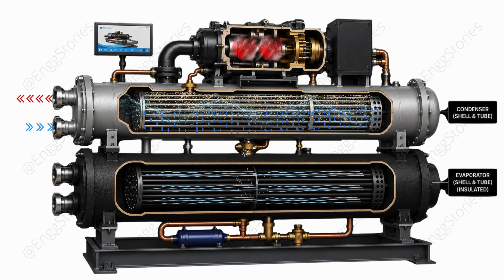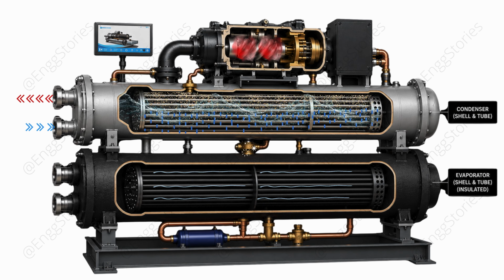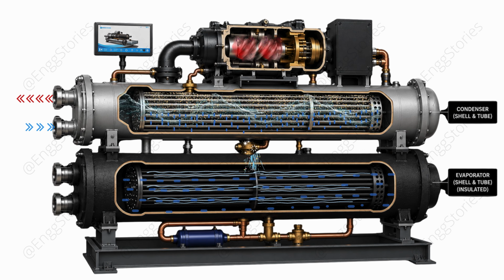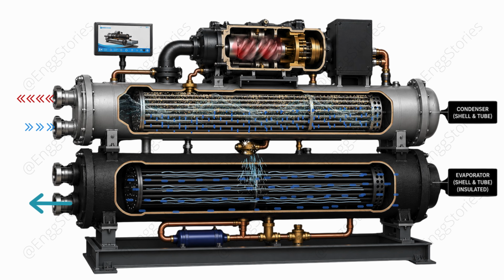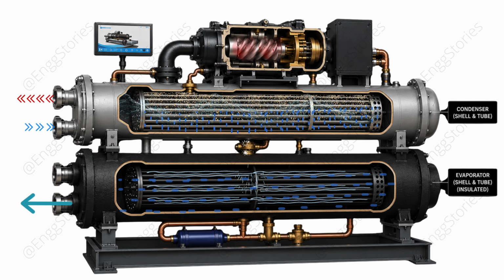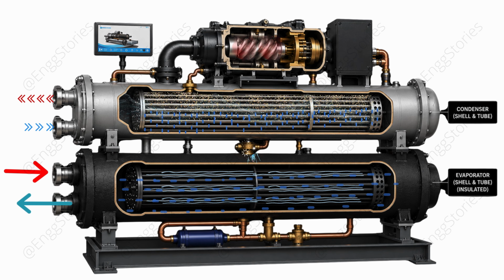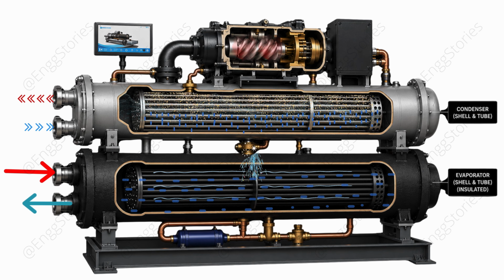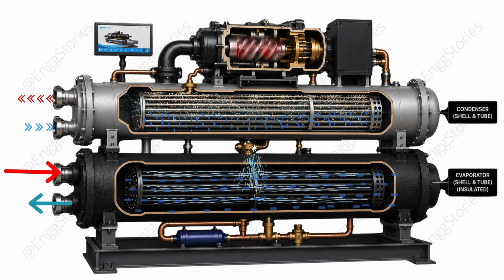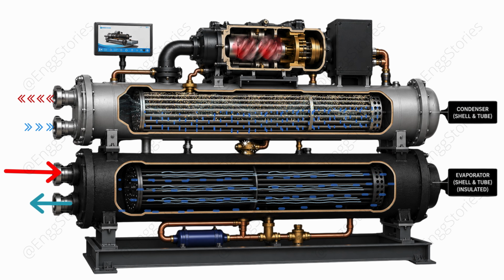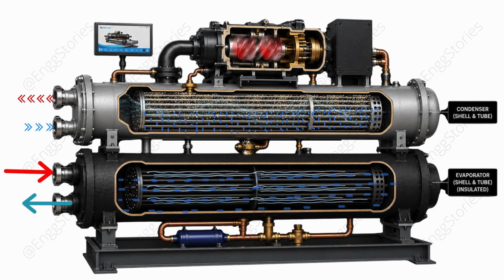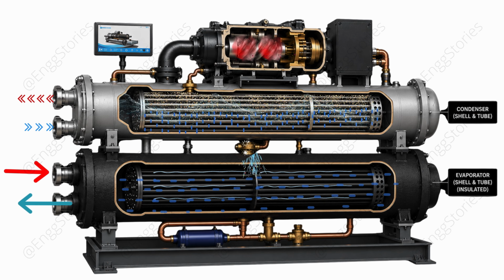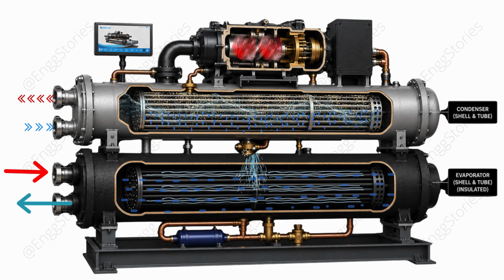The evaporator is filled with refrigerant, while the chilled water flows through the tubes inside it. The chilled water is pumped to the AHUs, where it absorbs heat from the building. It then returns to the evaporator, carrying this heat. Here, the refrigerant absorbs the heat from the warm chilled water and evaporates into a low-pressure, low-temperature vapor. This vapor then returns to the compressor, and the entire cycle keeps repeating to maintain a comfortable temperature inside the building.